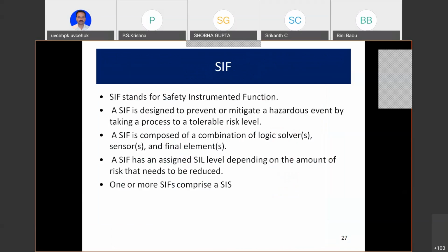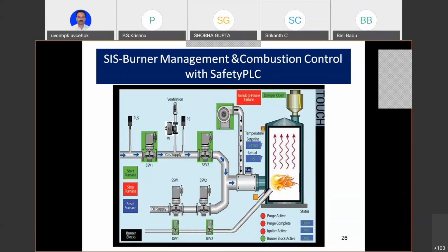Right. Then we start talking about a safety instrumented system, which is the SIS, the boss. The boss has subordinates, which are called safety instrumented functions. Now, let us look at this particular thing which we saw. I would call it SIS, burner management, combustion control. Let us say I'll purposely call it SIF. Suppose there was another burner like this, and there was a master controller also. That I would call a SIS, and I'll call all these things SIFs, because they become the sons of the SIS. So a SIS can have a number of SIFs.